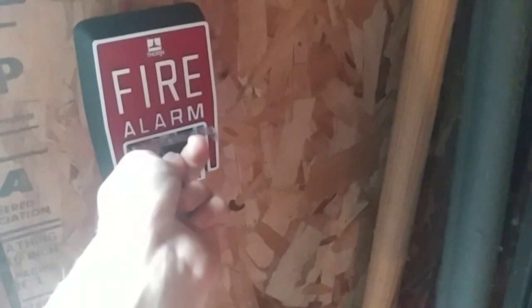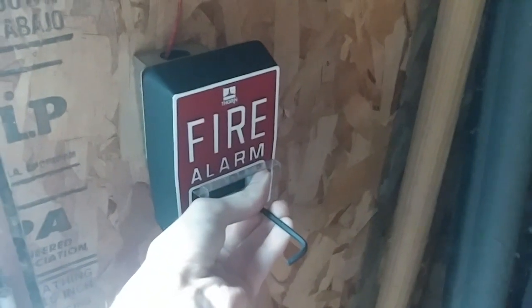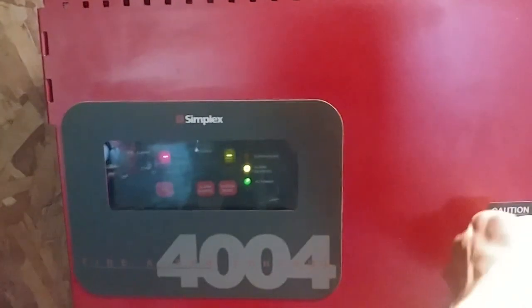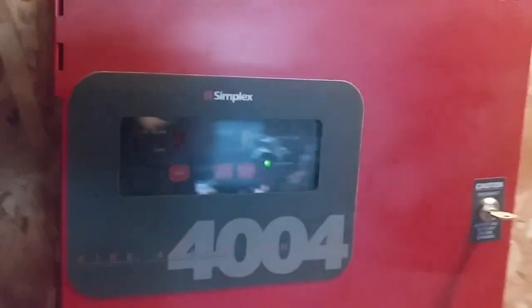Man, I think it's pretty loud, to be honest. Those electromechanical horns are pretty loud. All right, we're resetting this with one hand. I might have to finish resetting this off camera. All right, the pull station has been reset. While I was resetting this off camera, the system went back to alarm — I don't know why that happened, that's really strange. But we can do a final system reset, give it a few seconds here, and bam, just like that. I really like how this panel actually resets — it's pretty cool.